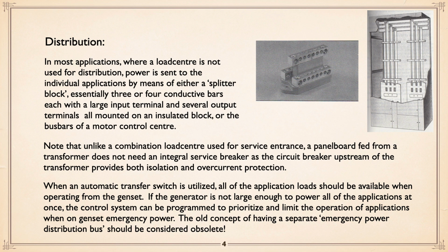One thing, if you have an automatic transfer switch and a generator for standby power, and we'll get into that much later, you basically should have the whole service provided from the generator if you don't have utility power. At one time, they used to have the expression emergency loads, which is a complex way of doing it. I think a far better way is to have everything fed, and then if you're worried about overload, if the generator is too small to handle everything, then you can set up your controls to sort of prioritize what is being attached to that load based on its importance and how heavy you're loading the thing.